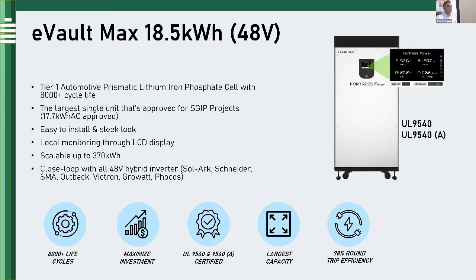What's also nice about this battery is that it's scalable up to 370 kilowatt hours. So not only will this work in a full home backup solution, but it can also work for commercial applications. This is 3-phase, 208 and 480 volt compatible. And lastly, the eVault Max has UL 9540 and UL 9540A certifications, so you shouldn't have any issues getting this permitted in the respective jurisdictions.